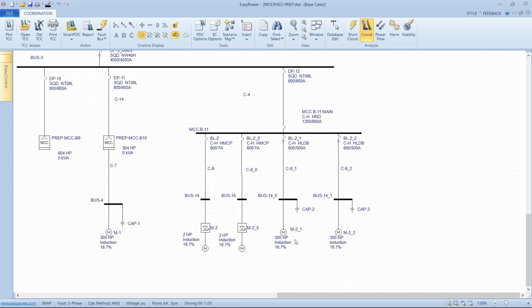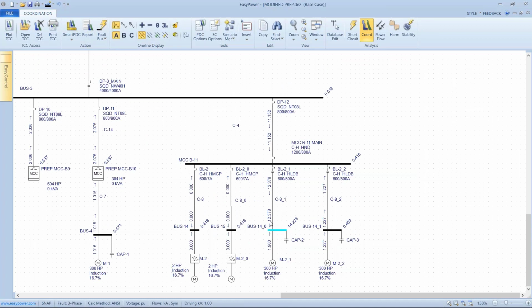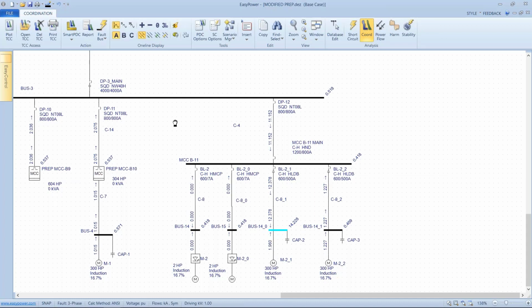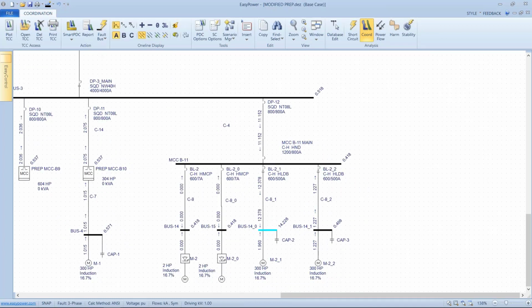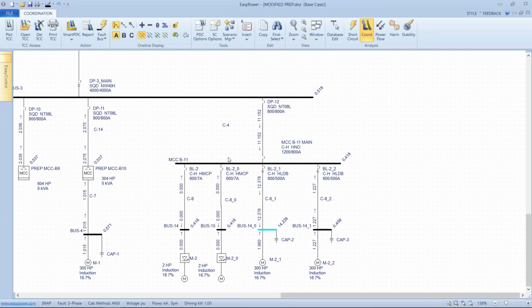So from a discrete implementation, the process would be, and this again is what I would suggest starting with: once I'm in coordination, pick out the single bus, go into current, fault that bus, and what we show in this case is the branch fault current. Because I've indicated remote current and voltage indications, if this bus faults, I'll have contributions from these other loads back through the connection point, and I'll have 7,000 amps coming from the utility and another 4,000 amps coming from these other loads. And in addition to that, this one large motor itself will contribute almost 2,000 amps.